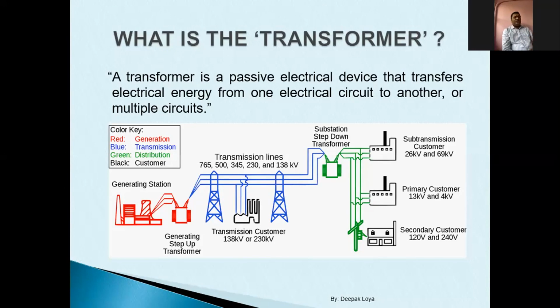Here in the presented diagram, you can see that there is a generating station. If you look at the older versions of power plants or generation plants, the voltage levels were around 6.9 kV. Then it moved to 11 kV, then to 21 kV. Now even 33 kV generators are available.